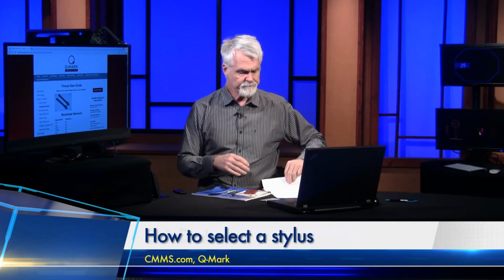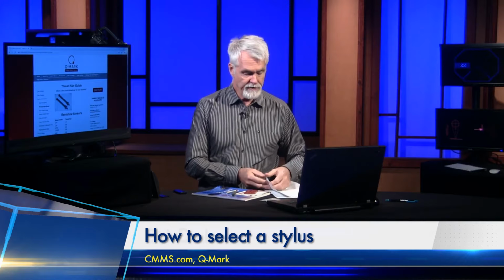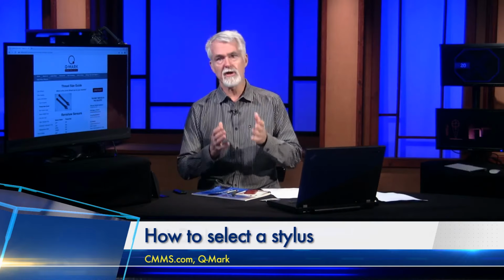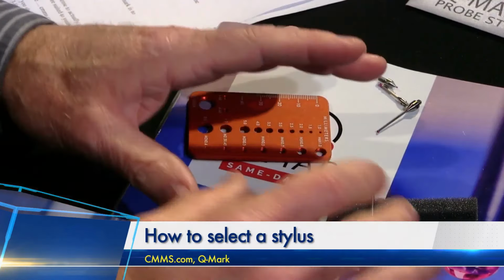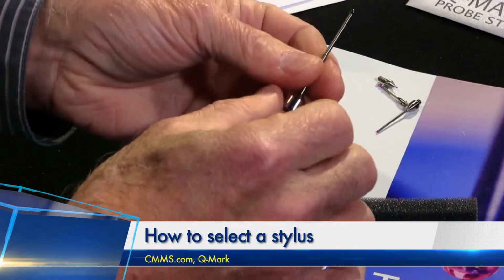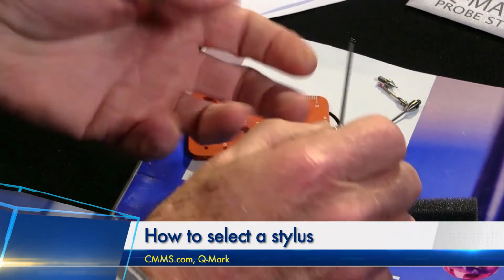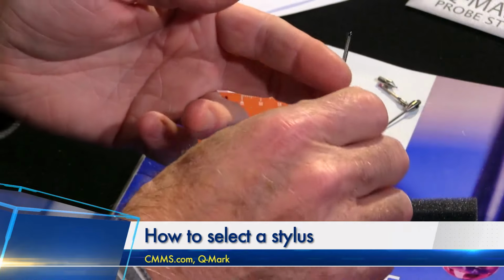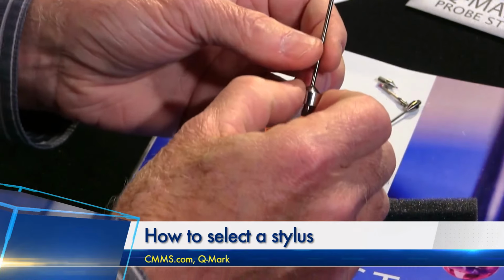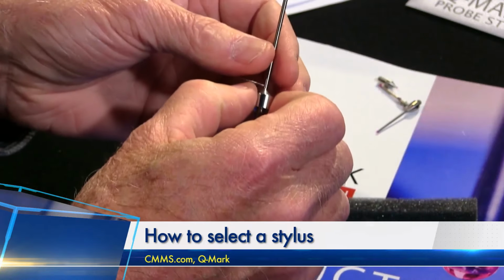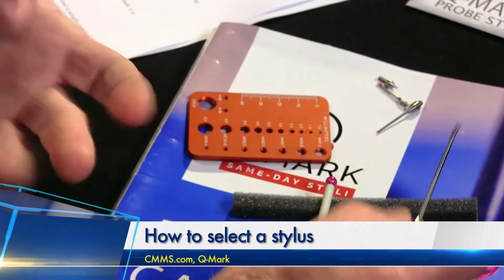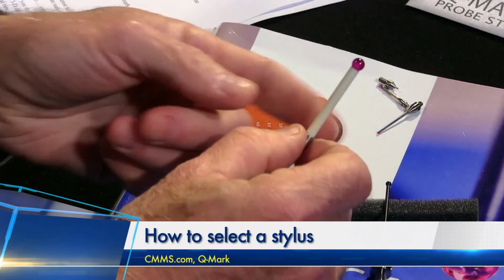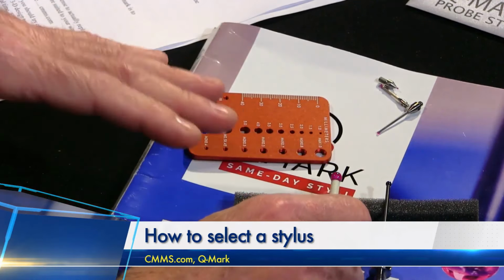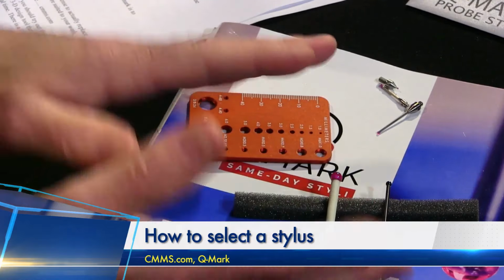So the other question is, how is the probe going to be used? You know, what ball size do you need? What shaft length do you need? What material do you need? There's a lot of different materials that styli can be made out of. So for instance, this one happens to be carbide. So you might choose carbide if you need a really rigid material. Carbide is typically used for that. If you need something lightweight, you might want to use carbon fiber or ceramic. This happens to be a ceramic one. Thermal stability, if that's important, you might use titanium or carbon fiber.